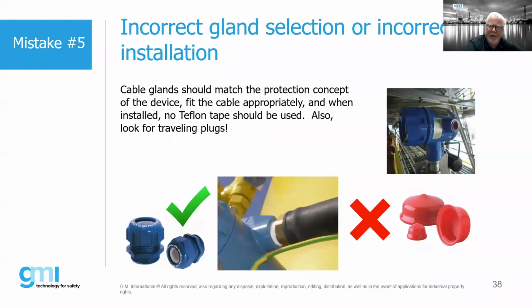A couple things on cable glands. Number one, down at the bottom, we do not want to use Teflon tape. We see that an awful lot. On the right-hand side, you'll see a transmitter with what is called a traveling plug. That's a non-certified plug. We would want to make sure that that plug is replaced with a certified plug.